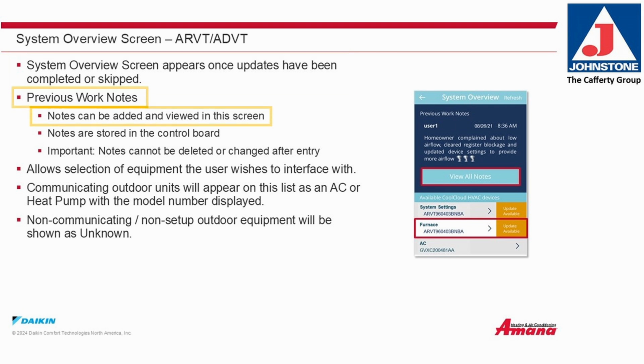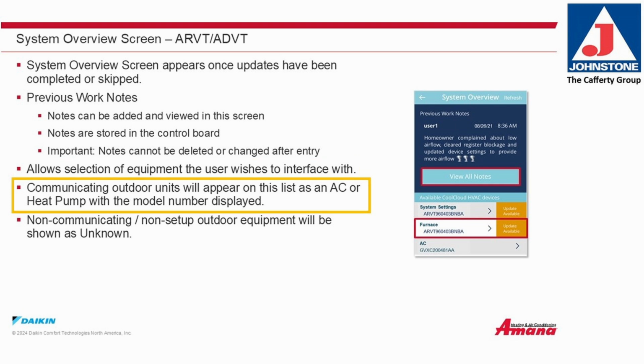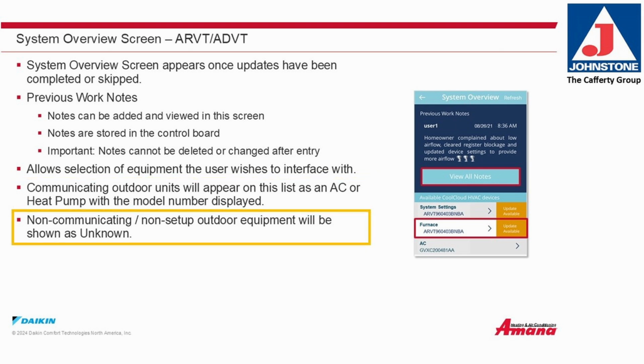Previous work notes. Notes can be added and viewed in this screen. Notes are stored in the control board. Important notes cannot be deleted or changed after entry. This allows selection of equipment the user wishes to interface with. Communicating outdoor units will appear on the list as an AC or heat pump with the model number displayed. Non-communicating or non-setup outdoor equipment will be shown as unknown.